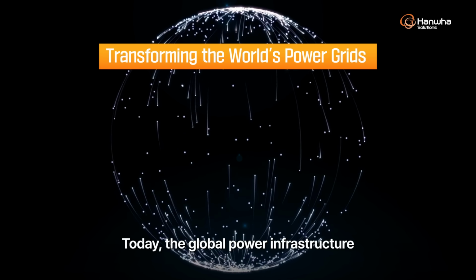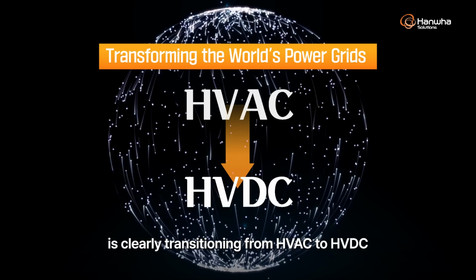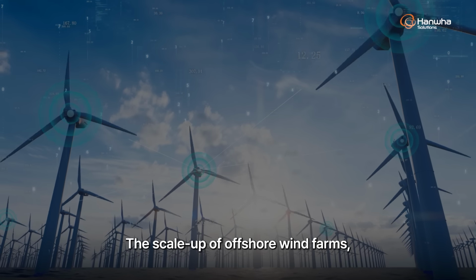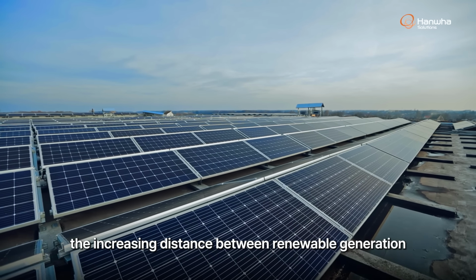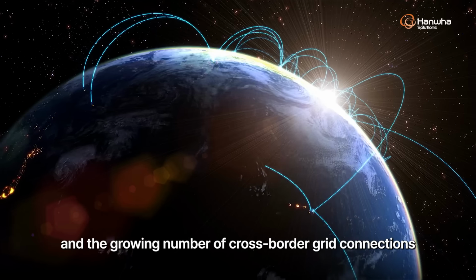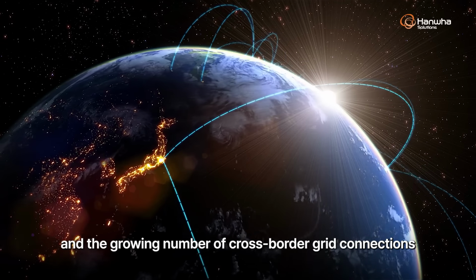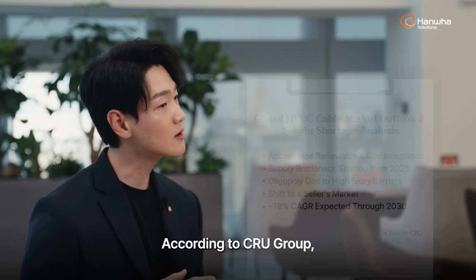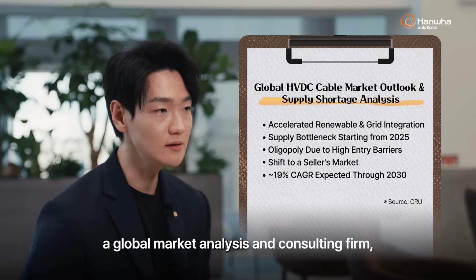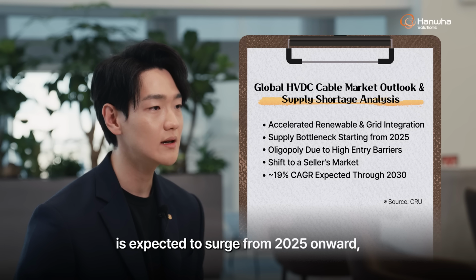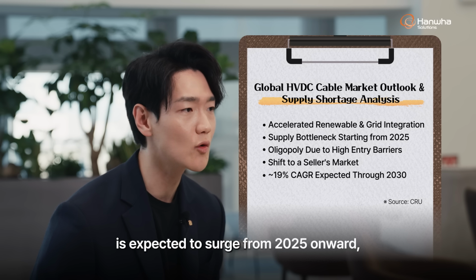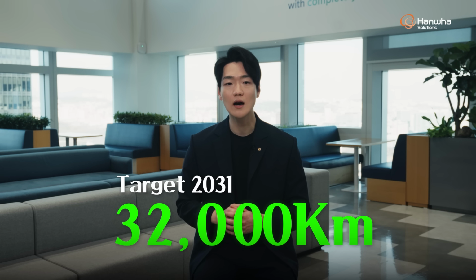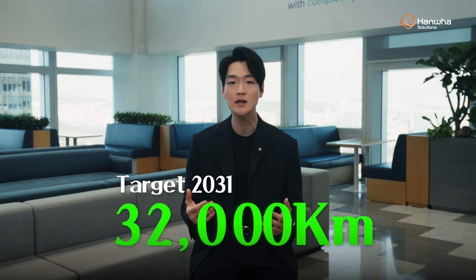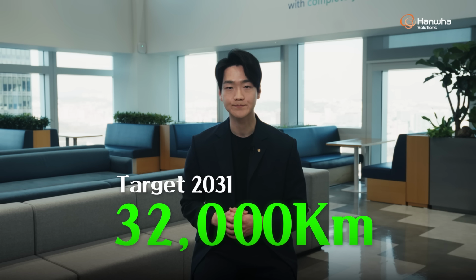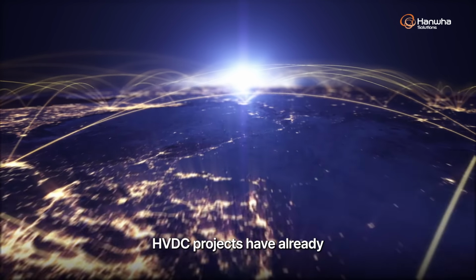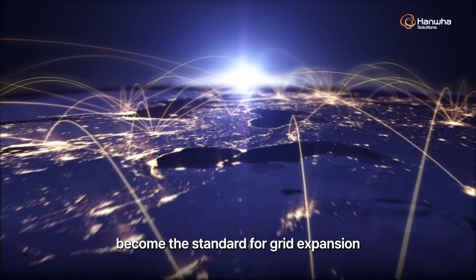Today, the global power infrastructure is clearly transitioning from HVAC to HVDC. The scale-up of offshore wind farms, the increasing distance between renewable generation sites and load centers, and the growing number of cross-border grid connections all demand HVDC solutions. According to CRU Group, a global market analysis and consulting firm, HVDC cable demand in Europe is expected to surge from 2025 onward, with approximately 32,000 kilometers of new HVDC cables projected to be installed by 2031. In Europe, China, and the Middle East, HVDC projects have already become the standard for grid expansion.